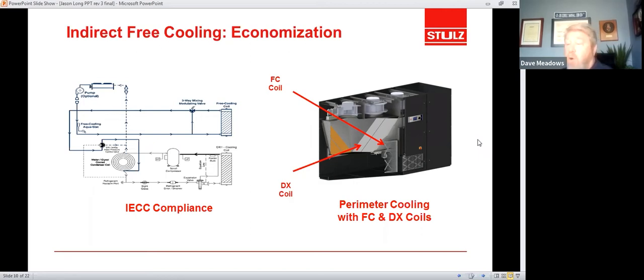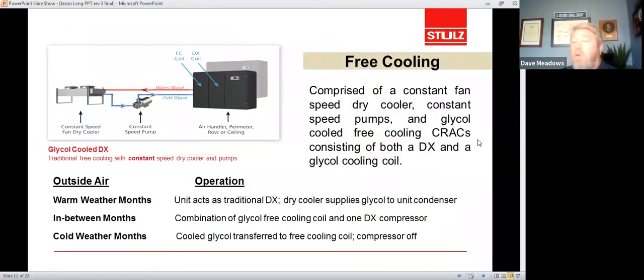Should the glycol not be cold enough to remove 100% of the heat load, then we can bring on the DX coil to provide cooling. And it's very important because with today's requirements for data centers, we'll see that utilizing a system like this leads to easy compliance with the International Energy Conservation Code, ASHRAE 90.1, the energy efficiency standard for buildings other than low-rise residential, and the new ASHRAE 90.4, which is the energy efficiency standard for data centers. The way the free cooling units work is that during warm weather months, the unit acts as a traditional CRAC unit. So we're operating the compressors as necessary to remove the heat load from the space.